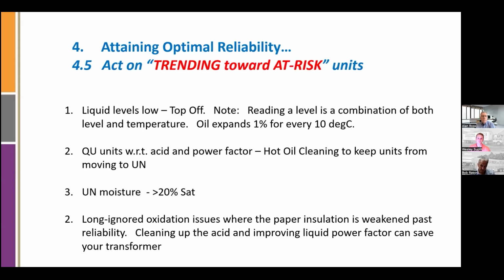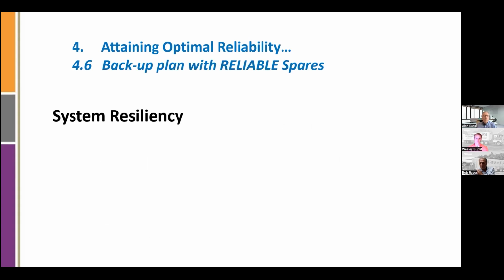Well, it has to become at risk. It doesn't get there overnight. It's something you can see. So trending toward at-risk units is our service-related category, which you can look at as being in between great and not good. What can you do in the middle? This is how you can extend the life of your aging transformers: don't let them become at risk. Stay on top of problems, such as when the level is becoming low, don't let it get too close to where you might have it overheat. Attend to increasing power factor, interfacial tension, and acid by oil reclamation, and keep the moisture levels low. Those are the tips we would give toward keeping an aging transformer from becoming unreliable.